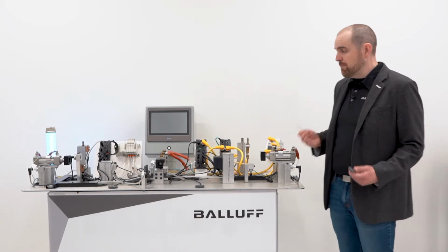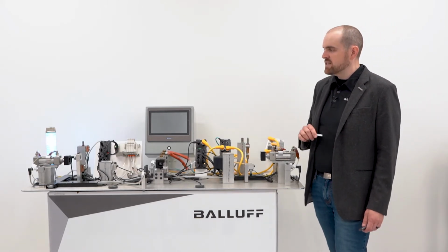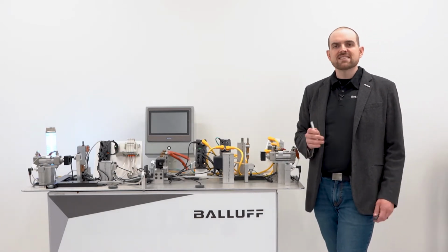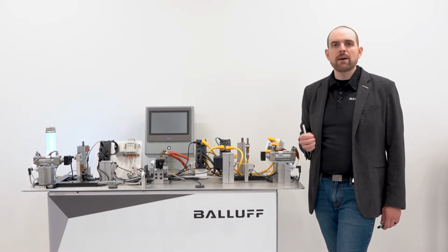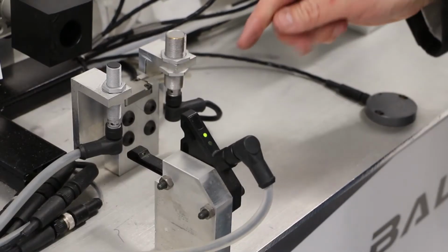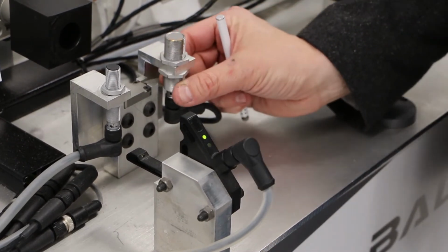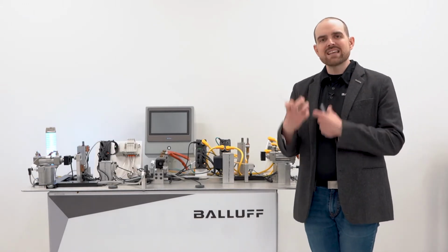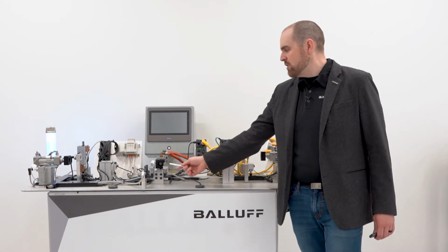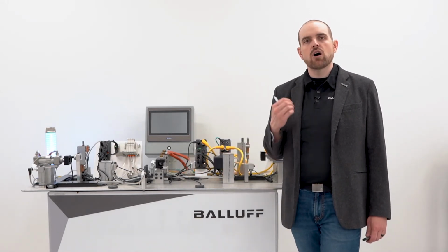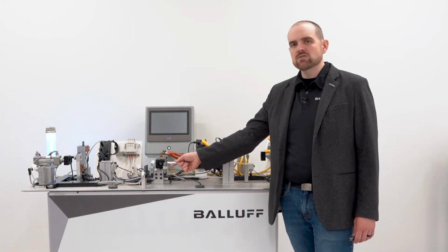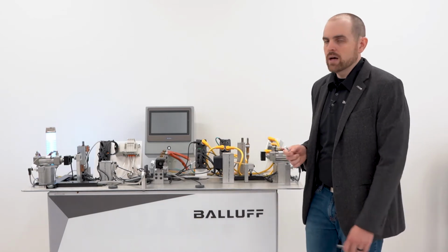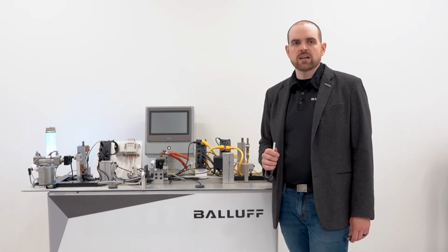Then, of course, for impact damage, you have steelface. You can see a steelface with PTFE coating here. I already mentioned the steelface with Sun 73 coating. But a steelface is designed to protect the sensor from impact damage. We also have a special sensor called the bunkerprox. It's a really cool design because it's using an M12 circuitry inside an M18 housing. So the housing itself is much more robust. If you have problems where the housing of an M18 standard sensor is getting sheared off or damaged, this is a much more robust housing. And so the bunkerprox is a great technology to be able to protect your sensors.